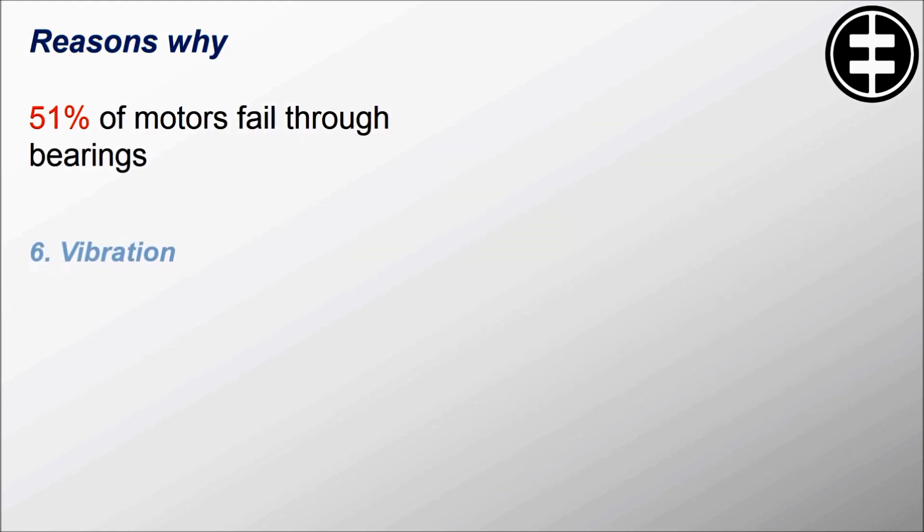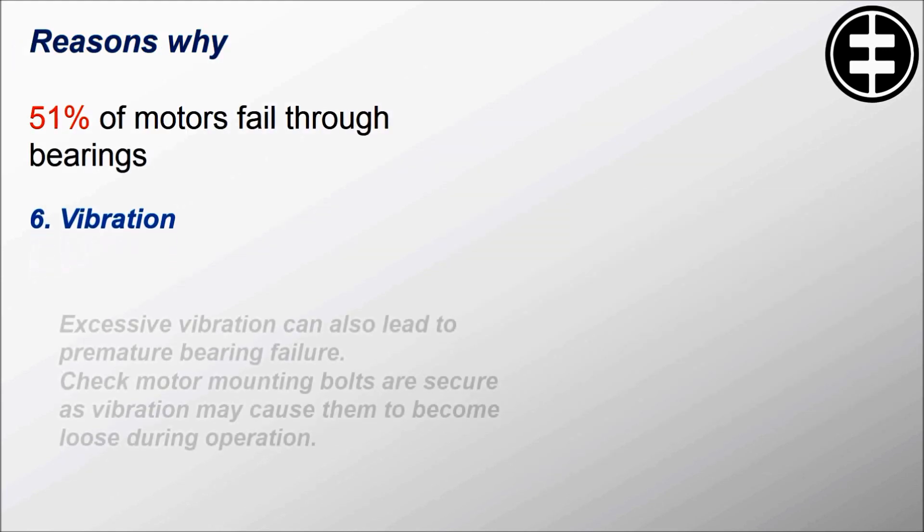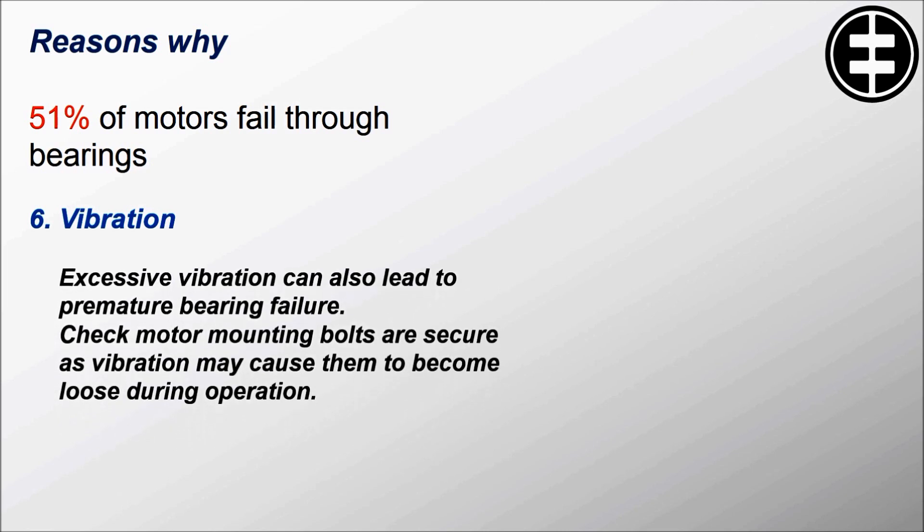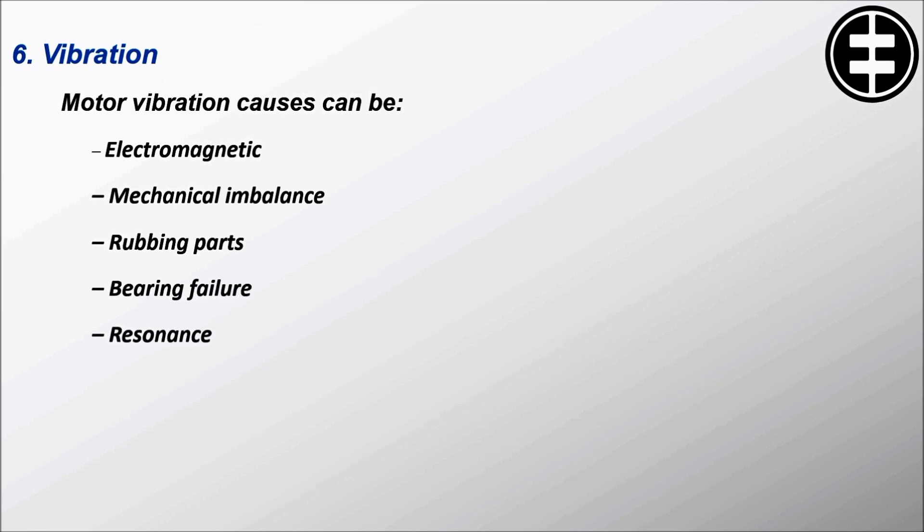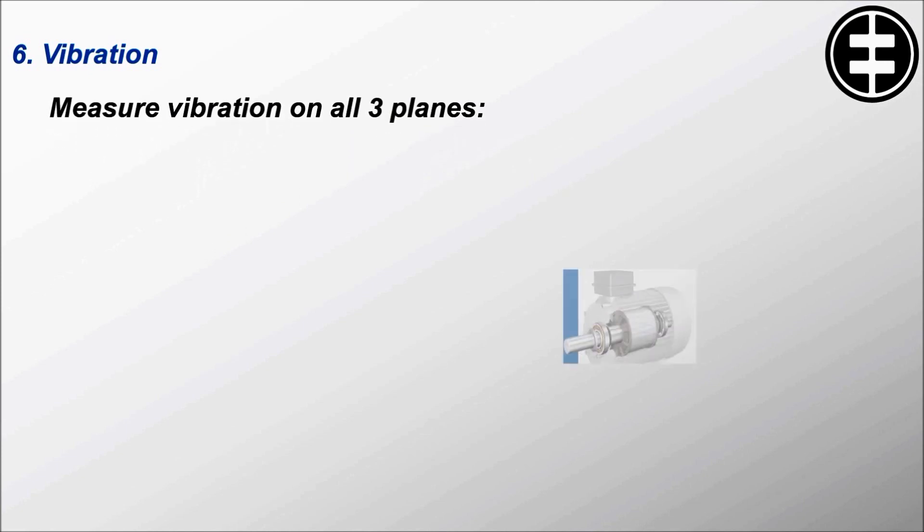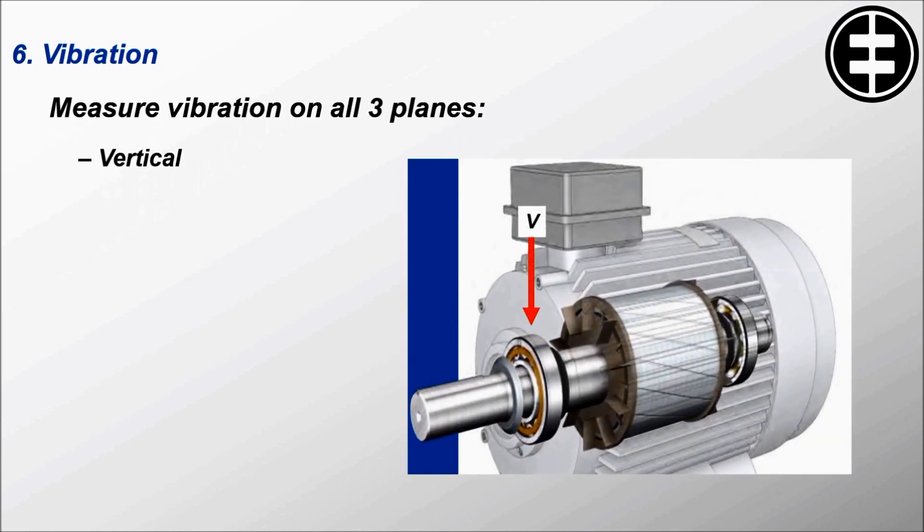Reason number six is vibration. Excessive vibration can also lead to premature bearing failure. Check motor mounting bolts are secure, as vibration may cause them to become loose during operation. Motor vibration causes can be electromagnetic, mechanical imbalance, rubbing parts, or bearing failure. Resonance. Measure vibration on all three planes: vertical, horizontal, and axial.